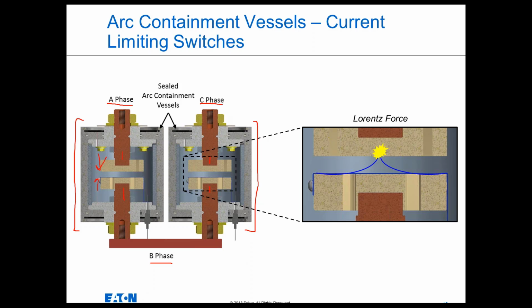That's how a lot of arc quenching or crowbar devices work. They essentially just tie all the conductors together very quickly in a zero impedance, creating that path of lower impedance, which quenches the arcing fault. But again, we didn't want to introduce a bolted fault to the system when there's an arc flash. So these contacts are actually fixed in place. This air gap does not change under any conditions. And you'll notice I said air gap. These arc containment vessels are actually filled with atmospheric air. They're not vacuum bottles, because we actually want arcing to occur inside these vessels under certain circumstances.